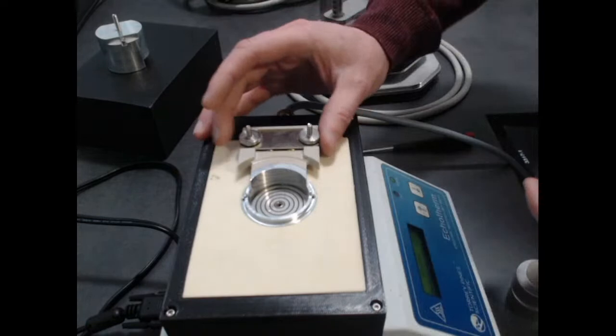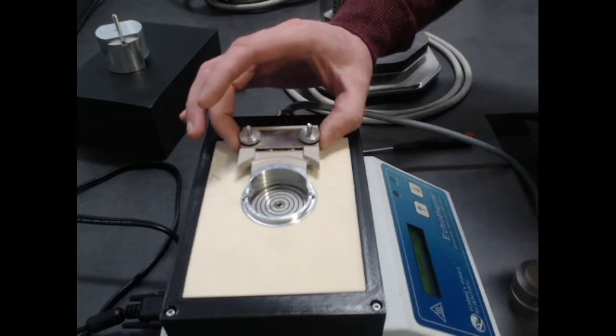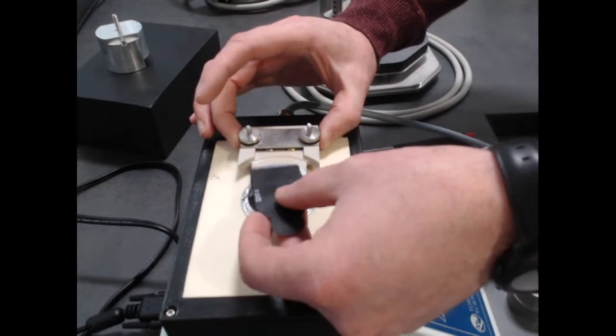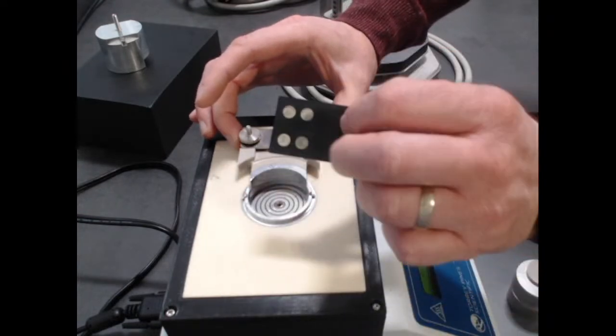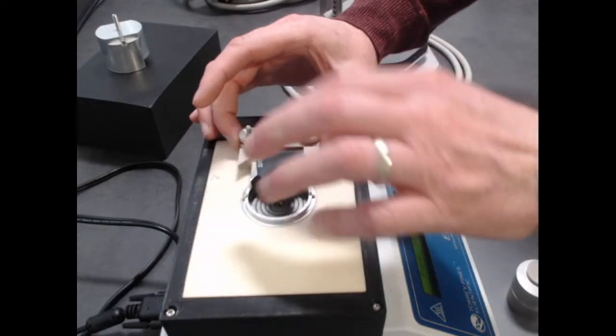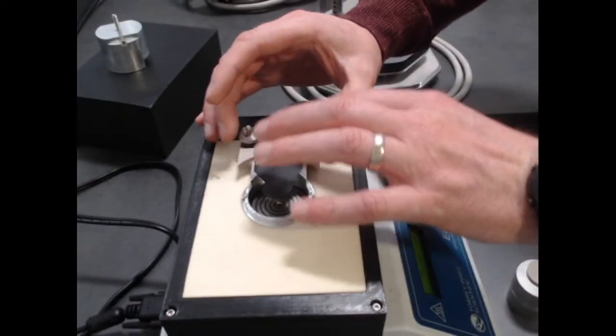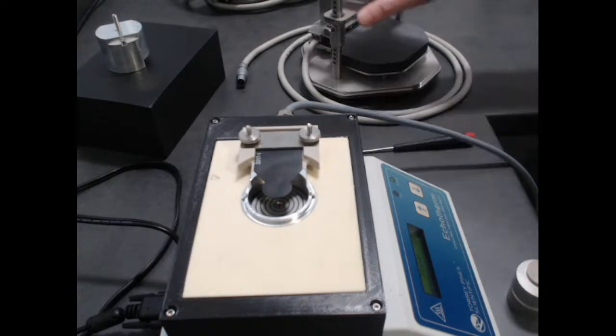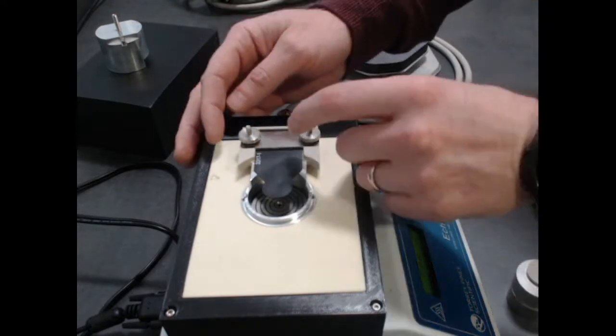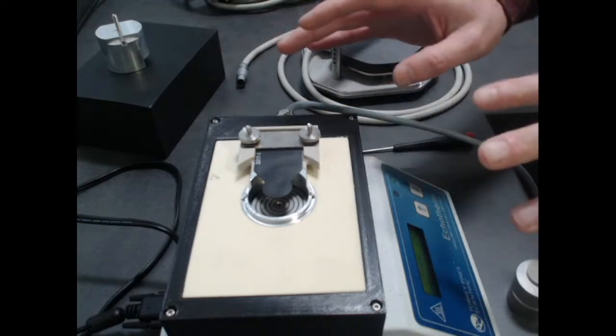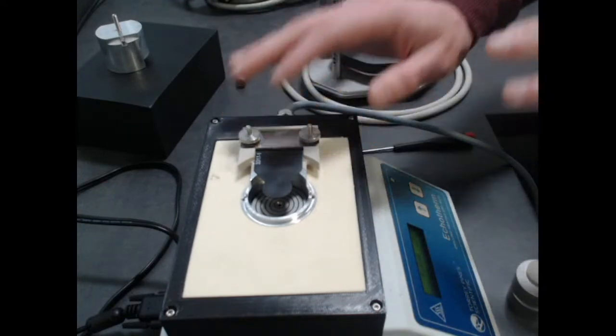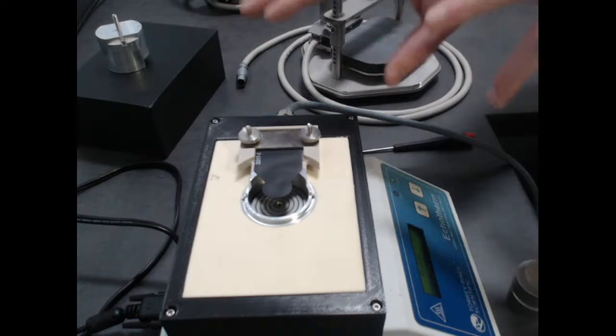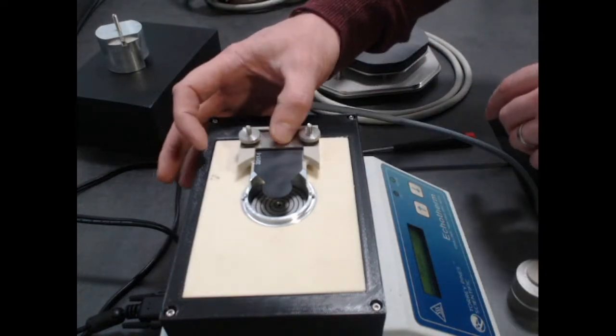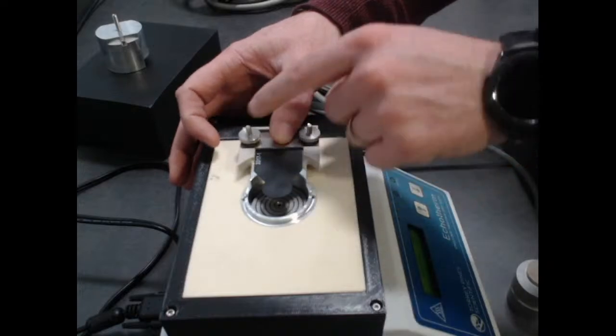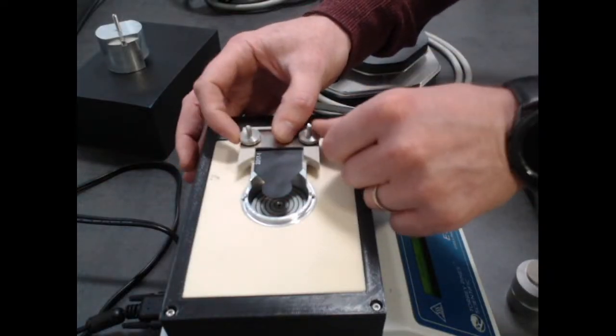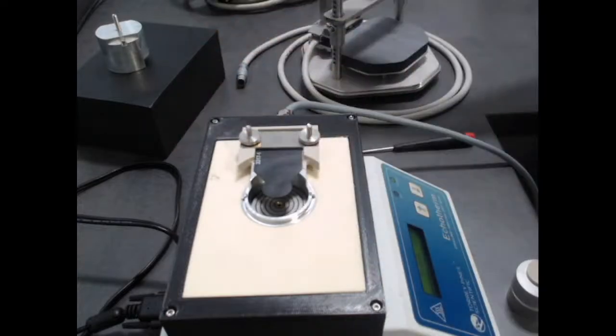So first, for setting up the sensor, we're going to back off the sensor contacts. We're simply going to slide the sensor's contacts down. For all of our devices, all of our adapters for running temperature, whether at room temperature or at different temperature ranges, we don't need cables on any of our sensors. All of our sensors come without cables. They don't need them because all the sensor connections are built into all of our devices. So by applying a little bit of pressure, we get equal distribution of force. We can turn these down, just finger tight is all you need.